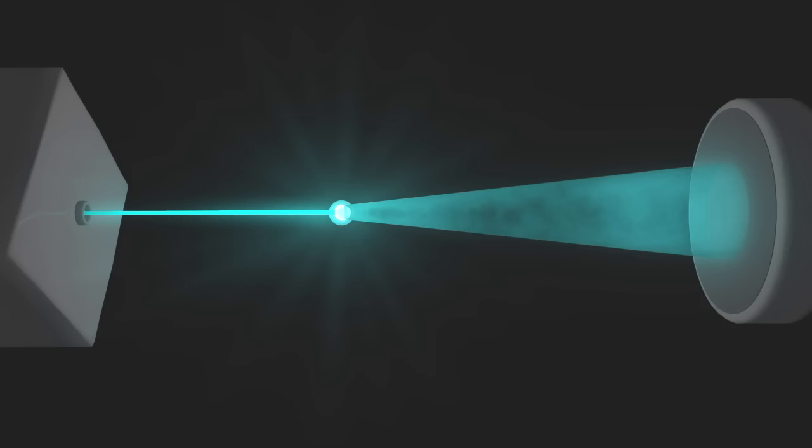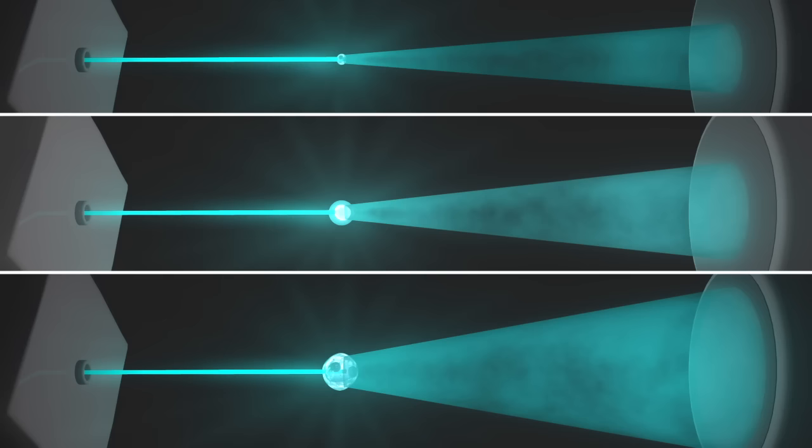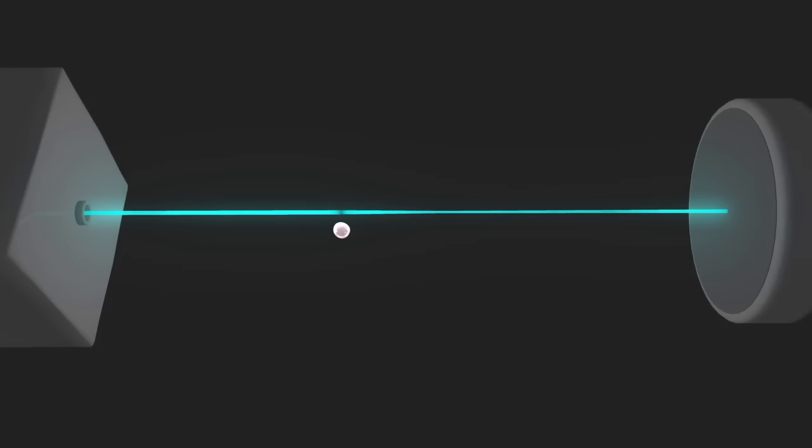The flow cytometer detects light scattered in a forward manner, called forward scatter, and light scattered in a sideways manner, called side scatter. The amount of forward scattered light for each cell is detected by a detector on the far side of the cell from the laser. Forward scatter is proportional to the size of the cell.